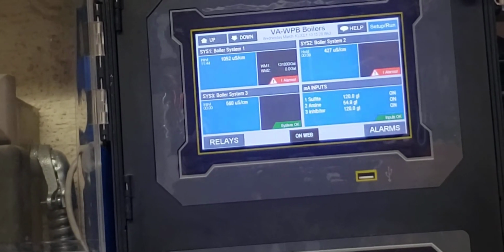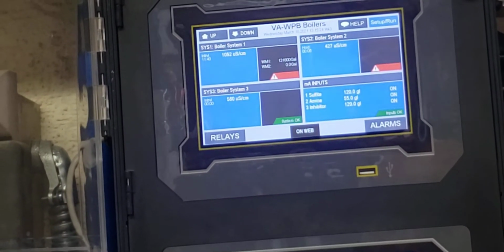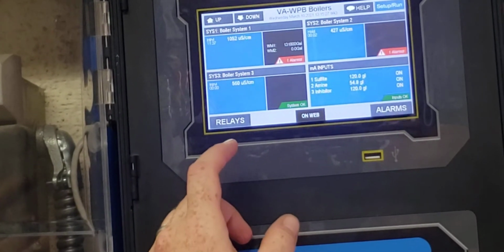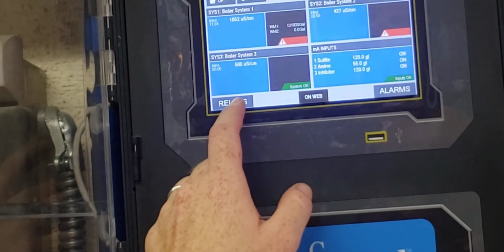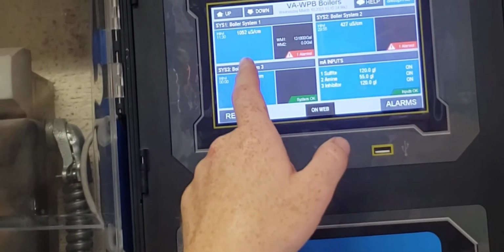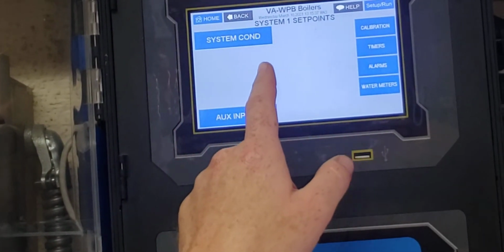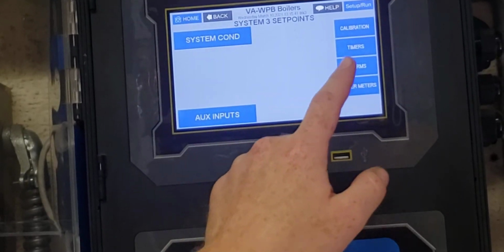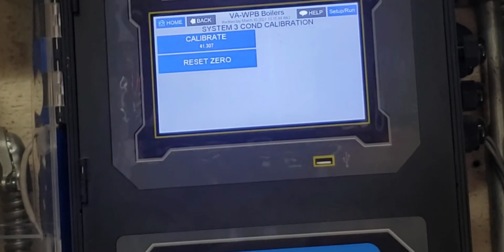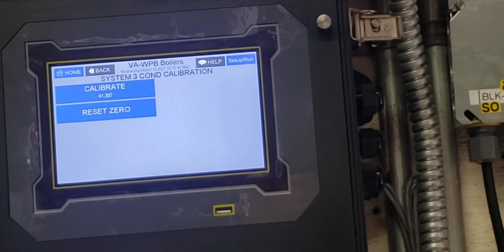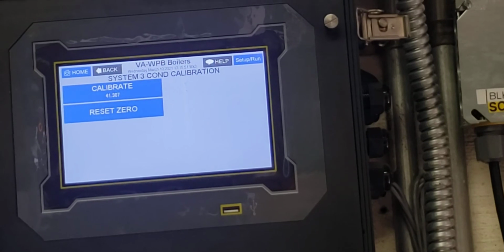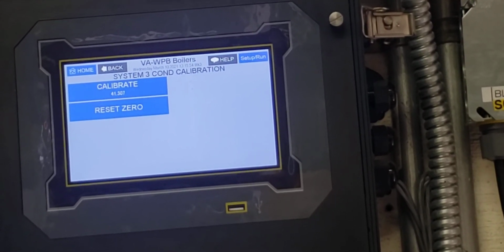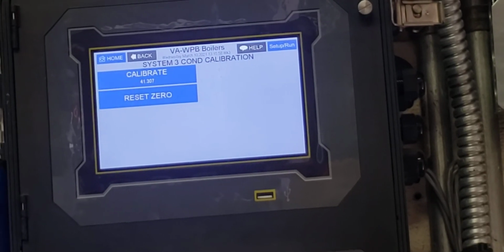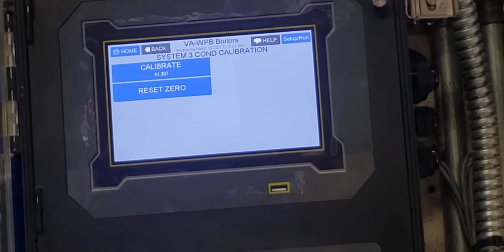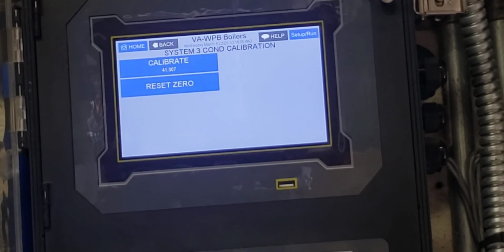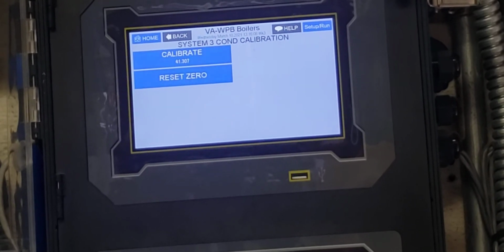And you can go back to that screen where it said reset to 0. Will that actually tell you what the conductivity meter is reading at that point, or does it zero it out to a point where it's giving you a true reading of what that probe is giving you right now? Correct. So here's a troubleshooting tip. If for some reason that particular probe will just not calibrate, you can do what's called a reset to zero. What you have to do though is turn off the valve at the boiler, take the probe out, dry it off, clean it, and reset it to zero, because in the air it should read zero. Then put it back in and do another calibration. That's what the reset to zero is.